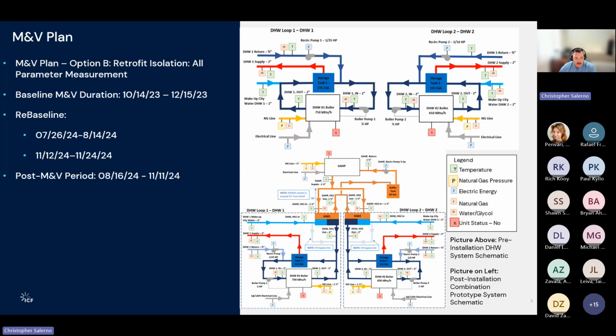It's designed to supply supplemental heating for the cold city water. And it says here, makeup city water. That's a term that was used internally. That really refers to the cold city water coming into the system and replenishing the tank from the hot water draw. So what we wanted to do is preload or preheat the cold water coming into those boilers, so that those boilers wouldn't have to warm that water up to replenish or refill the tank with hot water.